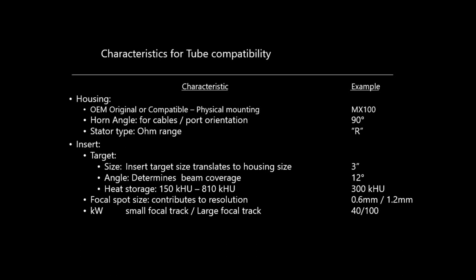Focal spot size, very important, contributes to the resolution. In the US, mostly we use 0.6, 1.2. In Europe, for instance, it's mostly 0.6, 1.0. And then you talk about the kW, which refers to how much power you put to each tube. How much power the tube is rated for. So these are the things that you're looking for when you compare two tubes. These are kind of the aspects that you're looking for.